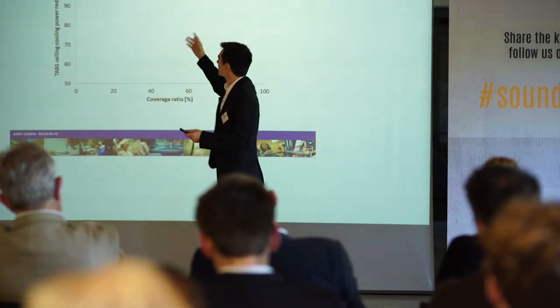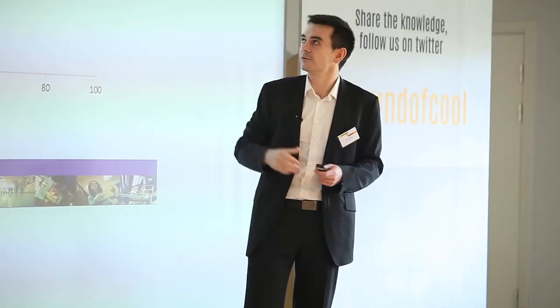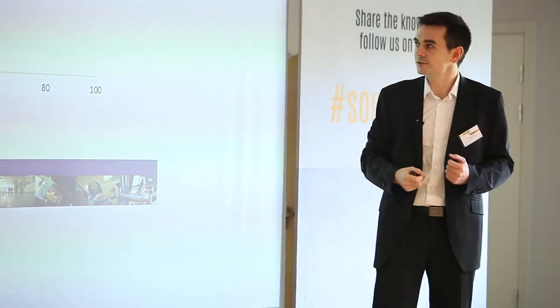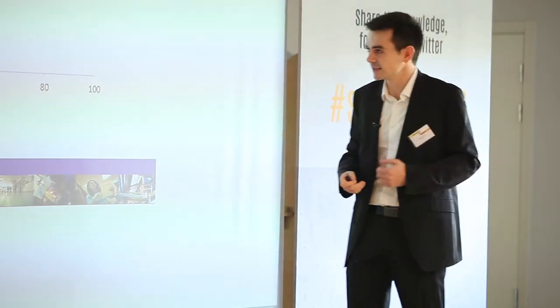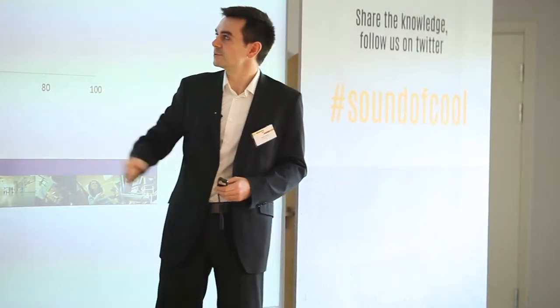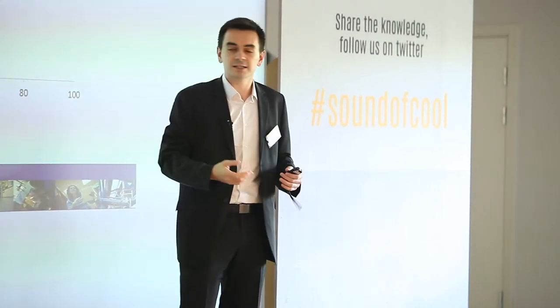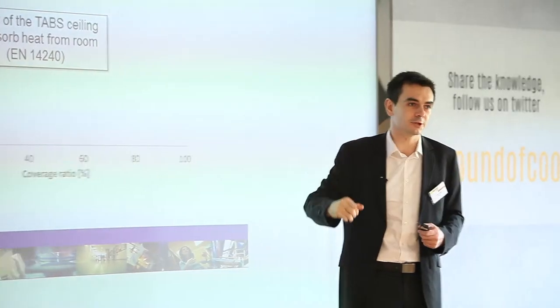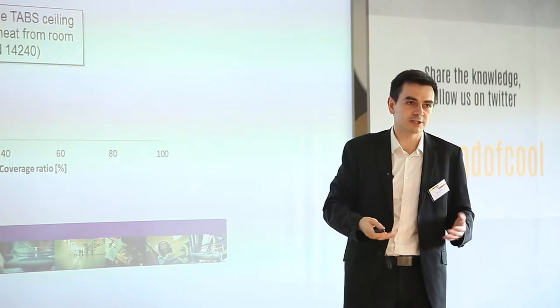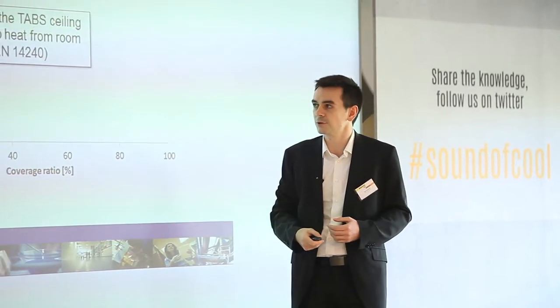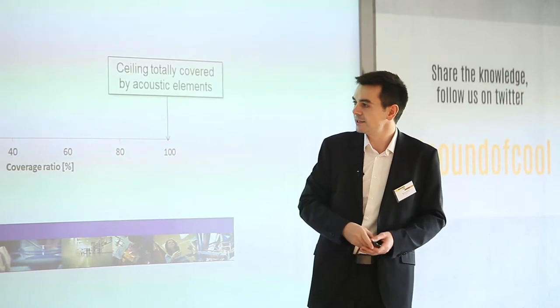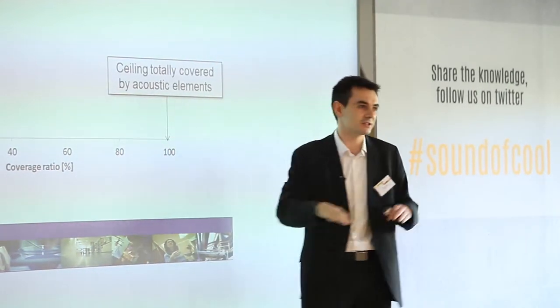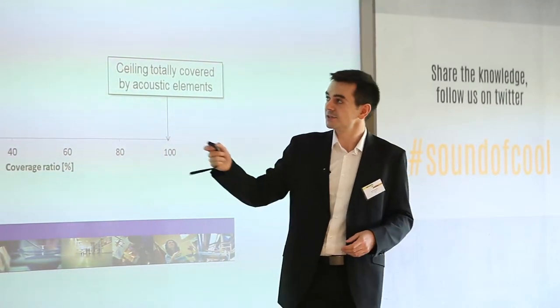I decided to use a graph from standard EN 14240, which is used to evaluate the cooling capacity of the ceiling. On this axis, we have the ability of the TABS ceiling to absorb heat. When it's 100, the ceiling works perfectly. When it's lower than 100, it means that something — the acoustic panel, for example — reduces the cooling power of the TABS. And here I plot the ceiling coverage ratio. If it's zero, it's a free ceiling; if it's 100, it's a ceiling fully covered with acoustic panels.